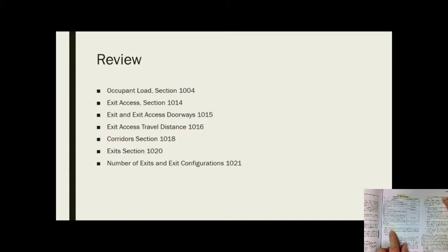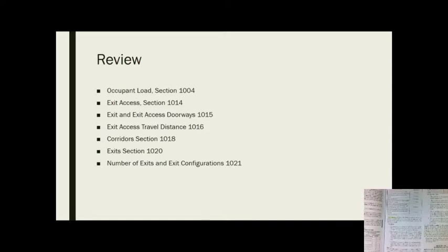There is also a term we're going to talk about, dead ends, when there's more than one exit or exit doorway, the length of that. That means you go down a hallway and it doesn't go to the outside. Most of the time your dead end corridor length has to be 20 feet, and that's it. But there are exceptions to that. You'll notice which groups give you 50 feet. So you need to be aware of those exceptions that are there.